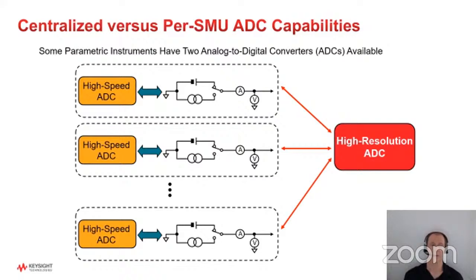Now, again, I just want to point out some parametric instruments actually have 2 analog to digital converters available. So typically, they might have a high resolution one, which is 21 or 22 bits, something very high, but it's a shared resource. And then they also sometimes have a per SMU ADC, which is, I would say, a high speed one, because obviously, if you're using that with the SMU, you can go much faster, but it has probably fewer bits, maybe like 16 bits. So you lose some resolution. But again, the trade-off is speed. So if you wanted to do, for example, true parallel measurement, you can't be using the high resolution ADC because that's a shared resource. And if you want to make a true parallel measurement, having everything measure at the same time, you need to make sure that you set your equipment up such that it's using the high speed or per SMU ADC and not the centralized ADC.